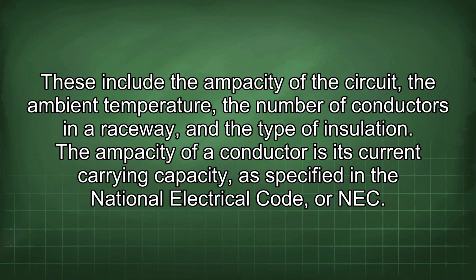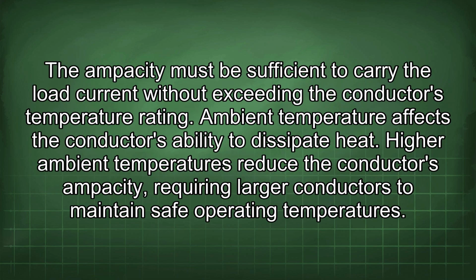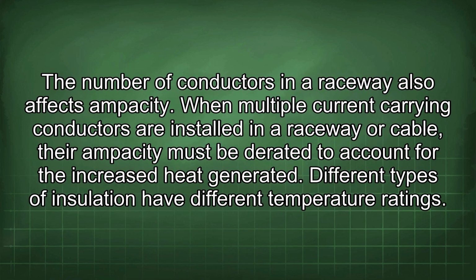of insulation. The ampacity of a conductor is its current carrying capacity as specified in the National Electrical Code, or NEC. The ampacity must be sufficient to carry the load current without exceeding the conductor's temperature rating. Ambient temperature affects the conductor's ability to dissipate heat. Higher ambient temperatures reduce the conductor's ampacity, requiring larger conductors to maintain safe operating temperatures. The number of conductors in a raceway also affects ampacity.